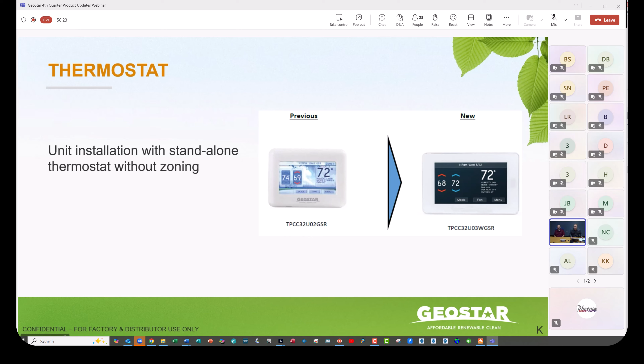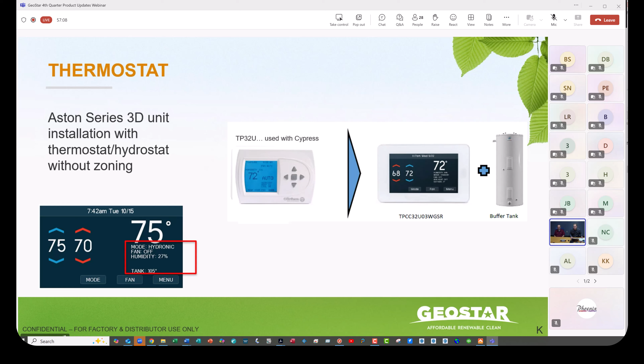This one is a little different, with a 3D series unit. In the Aston, we had the old push button thermostat, the TP32UO4, used with the Cypress. When we transitioned to the Aston 3D in the R454, that thermostat could not be used. So we introduced the Aston 3D unit with this new thermostat, also set up for hydronic functionality. We did require that you purchase our buffer tank with it, and we'll talk more about that buffer tank in a few minutes—that's the installation difference with Aston 3D.